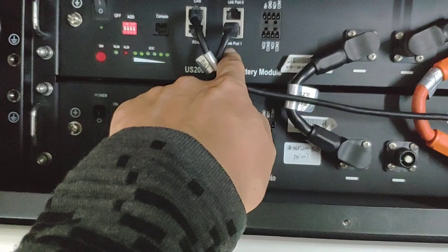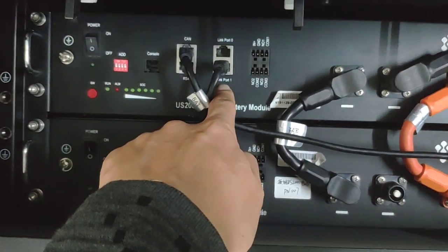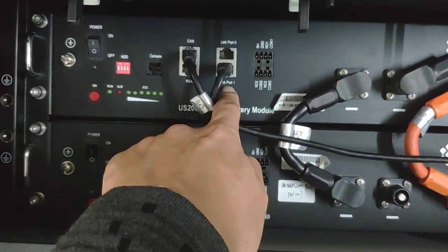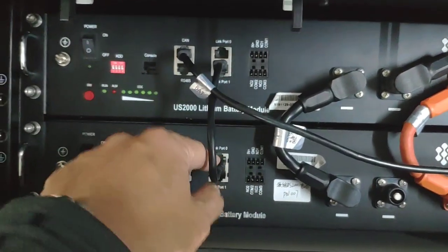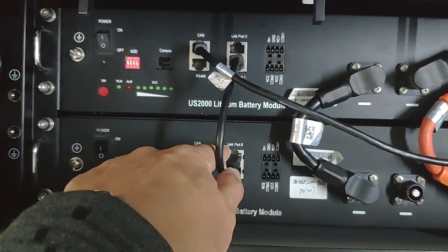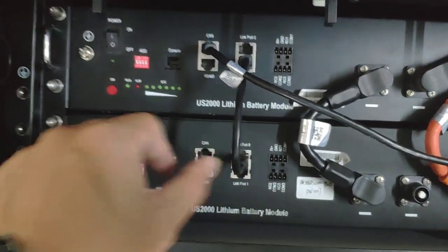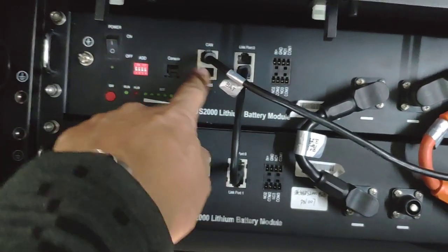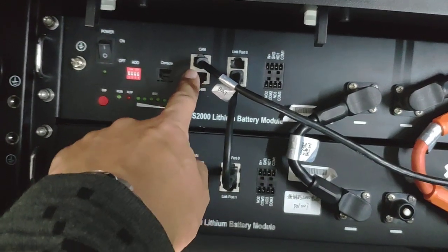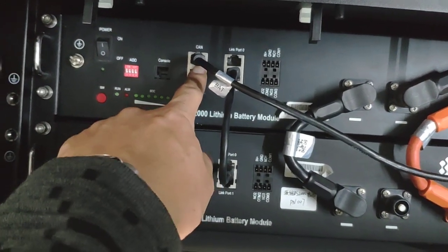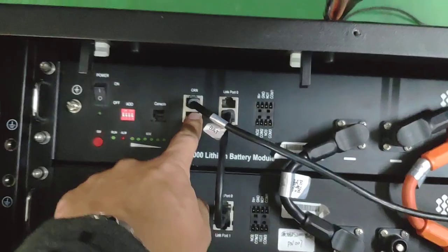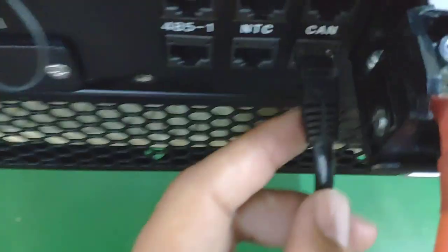The master battery must have the link port at link port 1, and it connects to the second battery at link port 0. Also, the communication cables communicate from the master here and connect to the hybrid inverter.